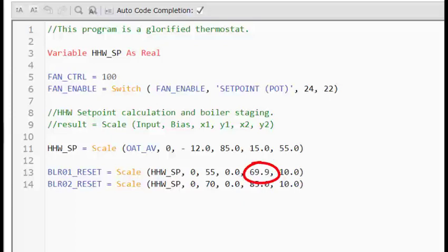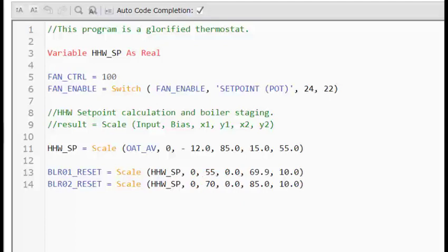Once the scale function sees 69.9 degrees as a set point, it will be outputting 10 volts to the first boiler. Then when the heating hot water set point is at 70 degrees, boiler number two starts to receive its 0 to 10 volt signal until it's 10 volts at the calculated value of 85 degrees.